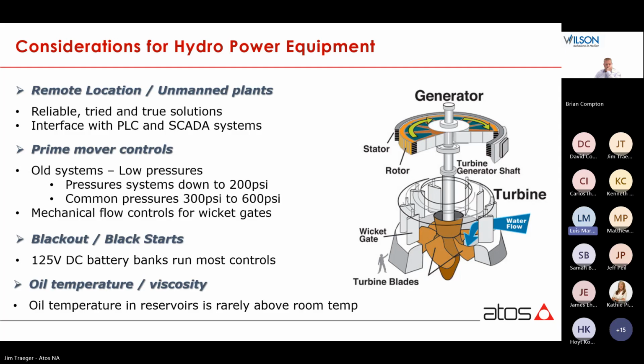Considerations for hydropower equipment. They are in remote locations and they are unmanned plants. Reliable, tried and true solutions are required. Also, knowledge of interface with the PLC and SCADA communication systems. For prime mover controls, they are old systems. They operate at low pressures, around 200 psi. Other common pressures are 300 to 600 psi. And they also have mechanical flow control wicket gates. For blackouts and black starts, they have 125 volt DC battery banks that run most of the controls in these systems. Oil temperature in hydraulic reservoirs is rarely above room temperature.